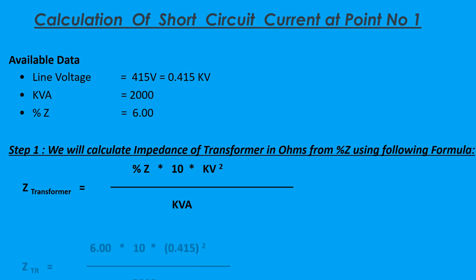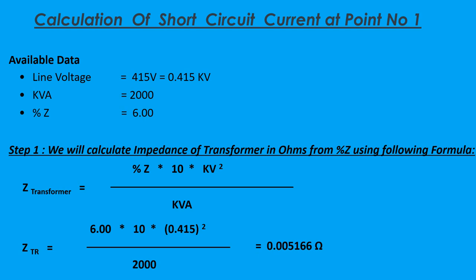For calculation of short circuit current at Point No.1, available data: line voltage is equal to 415 V (0.415 kV), KVA is equal to 2000, and percentage impedance is 6%. Step 1: We will calculate impedance of transformer in ohms from percent impedance using the following formula. Z transformer is equal to percentage Z multiplied by 10 and kV squared, divided by kVA. Therefore Z transformer is equal to 0.005166 ohms.